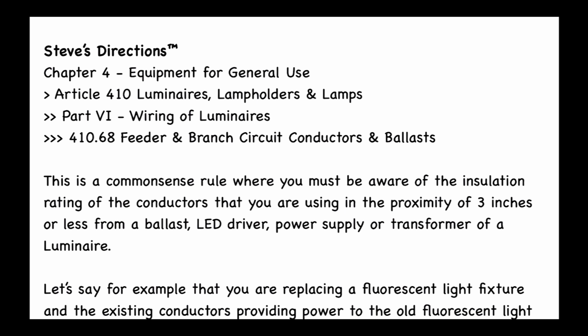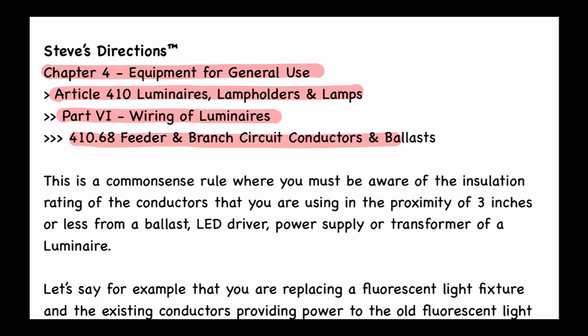All right, so we're in our textbook, and it is Article 410 for luminaires, lampholders, and lamps, within Chapter 4, Equipment for General Use. When we go to the article, we look at the parts, and we see Part 6, called Wiring of Luminaires. And then we find 410.68, feeder and branch circuit conductors and ballasts.